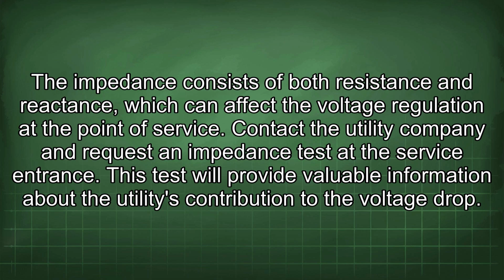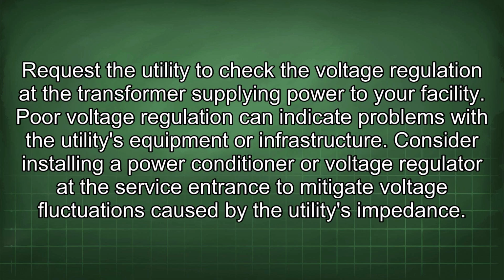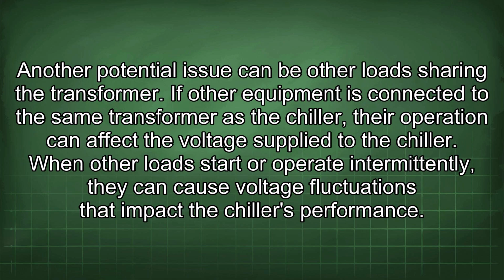This test will provide valuable information about the utility's contribution to the voltage drop. Request the utility to check the voltage regulation at the transformer supplying power to your facility. Poor voltage regulation can indicate problems with the utility's equipment or infrastructure. Consider installing a power conditioner or voltage regulator at the service entrance to mitigate voltage fluctuations caused by the utility's impedance.